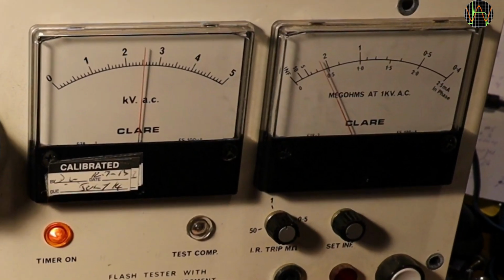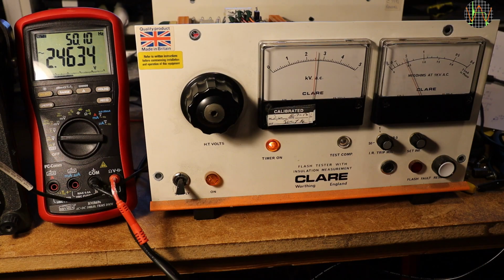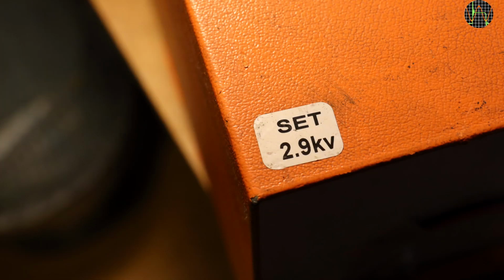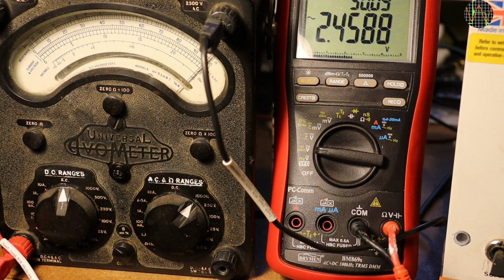2.46 kilovolts, and with a 2.5 megohm load we should see nearly 1 milliamp, but instead it's approaching only 0.5 milliamps. I think the current/megohm meter has been wrongly calibrated, and I think this was done on purpose, because there is a sticker on the box. If the meter was calibrated to show megohm at 2.9 kilovolts instead of 1 kilovolt, my results would make sense. Unfortunately, I can't test at 2.9 kilovolts because the AVO 8 is already at its maximum. I have no idea why the previous owner had chosen this value, but I would rather have the original.